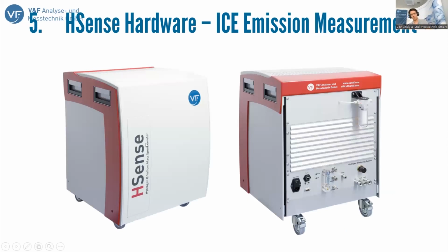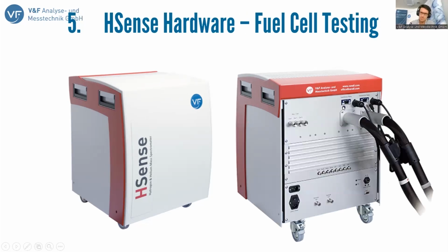So here we have a picture of how the instrument looks. This would be the internal combustion engine hydrogen sense. This is also the instrument that we are going to look at later on the live camera. And in comparison, here we have the fuel cell type HSense with the 2 sample inlets. And you see here there are these heated lines, which I've just shown in the schematic.